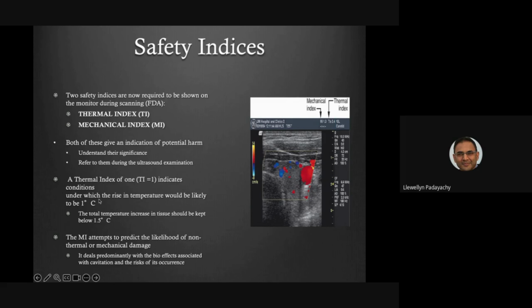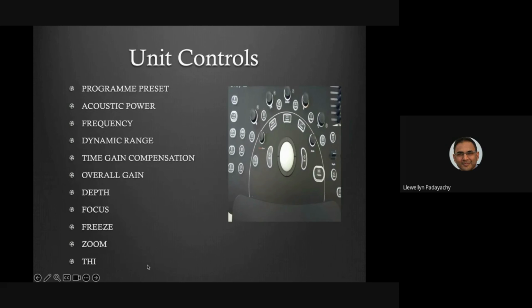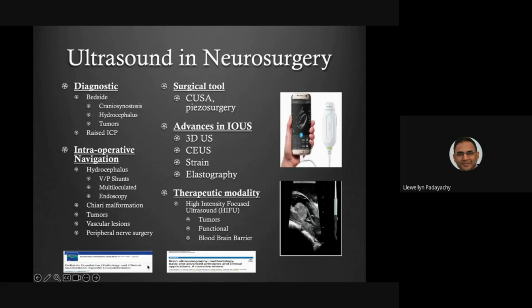Thermal index of 1 means the temperature rise in the body would likely be 1 degree. It must be below 1.5. And the mechanical index tries to predict the type of cavitation or non-thermal injury. So that must be within the safety limits. The program, the unit controls, I think those are things a lot of you will hopefully be familiar with.